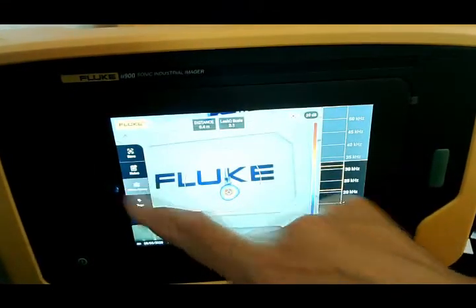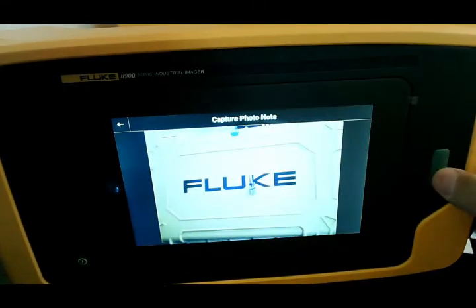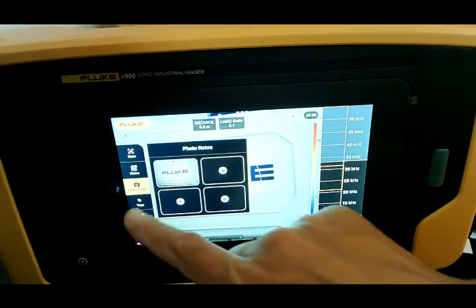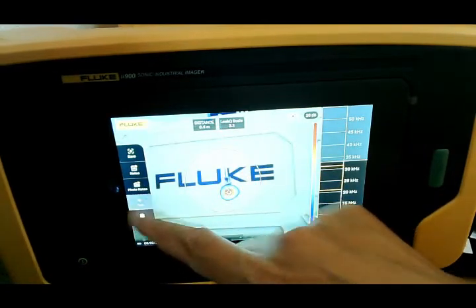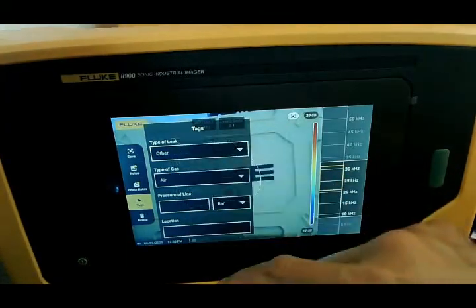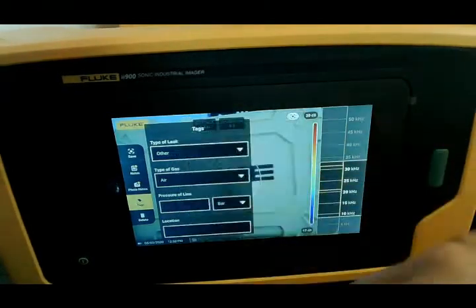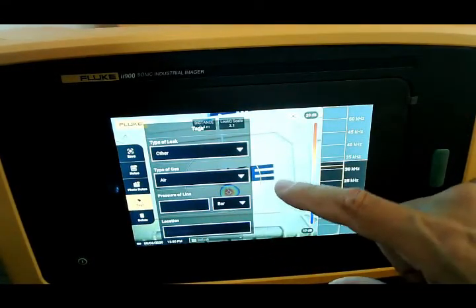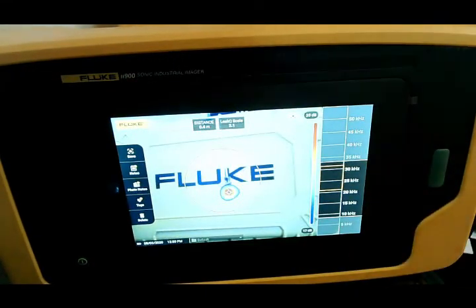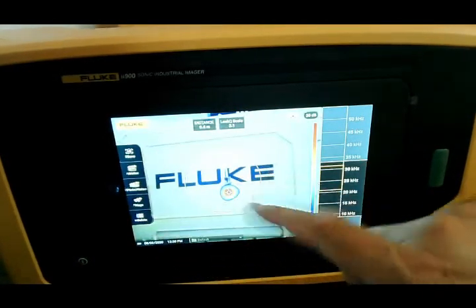From here I can actually add text notes that will save with the image. I can add reference photos — up to four images — including a live image of the valve, line, or name plate I'm working on. I can also add tags: the type of leak such as quick connect, threaded, hose, open, or other; the type of gas since we can also look for gas leaks, vacuum leaks; and then I can add the pressure on the line. This makes it a quick reference when I output it in the software.